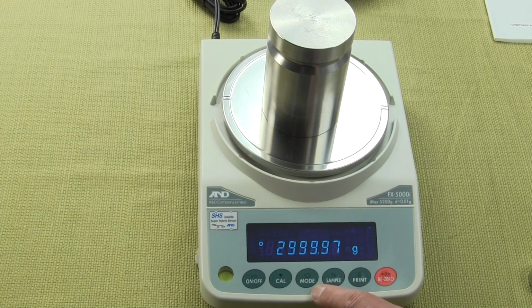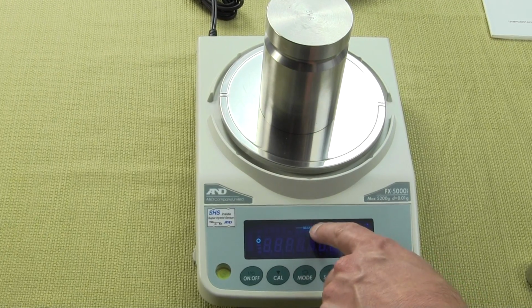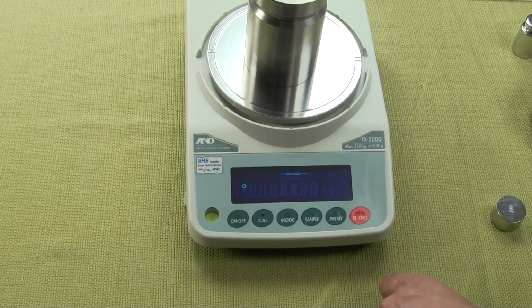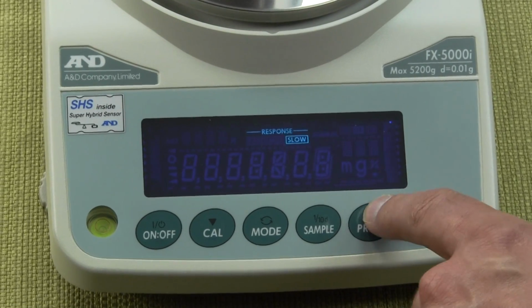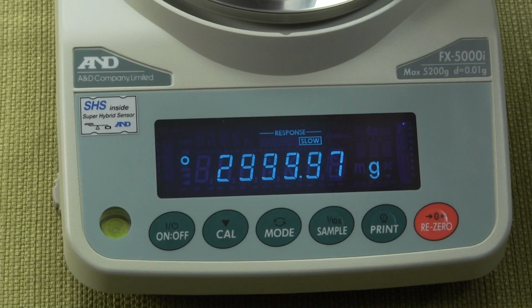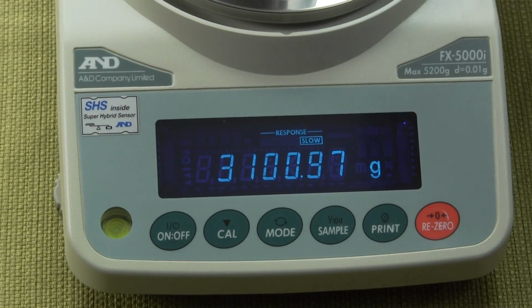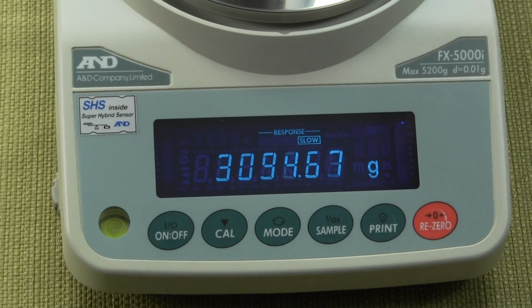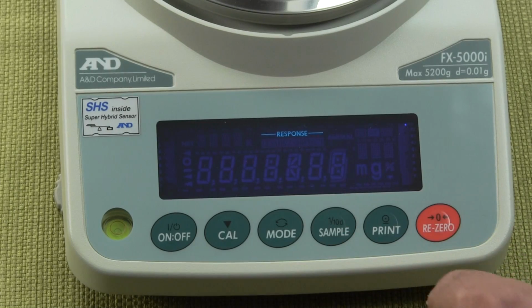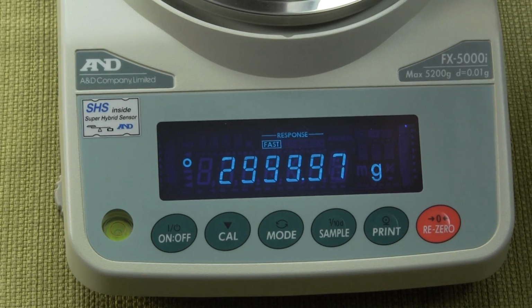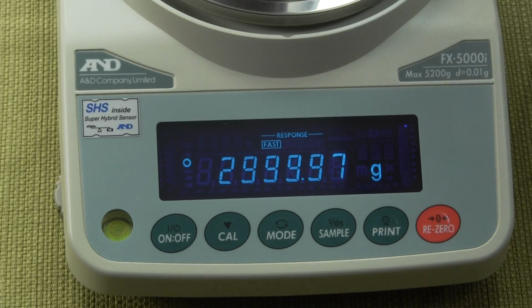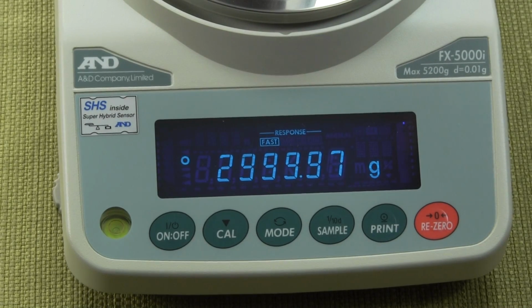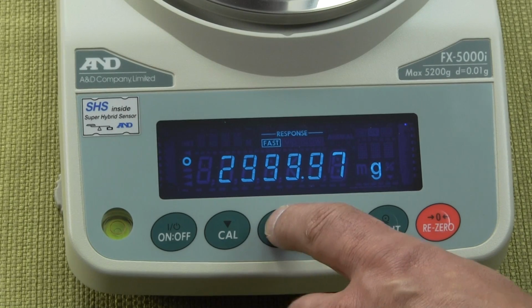So simply pressing down the mode button and holding it, you'll notice you have response, and then you have it in mid. To change this, one simply presses the mode key, and you can go to slow. And to store it, you're going to hit the print key, and then it will return. And so you can see the balance is a little bit slower in the slow mode. Okay, and now we'll go back and we'll change it to the fast mode. So now you notice it says fast. Hit the print button to store it, and you'll see how much quicker the response time is. Again, sometimes in unstable environments, the fast mode is too fast. And now we'll set it back to the default, which is going to be mid.